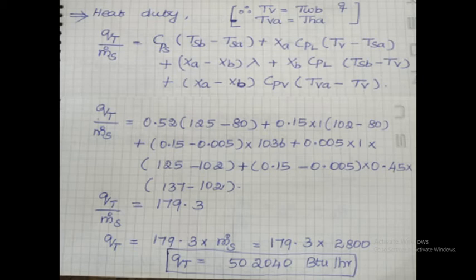TVA equals THA — that is the hot air outlet temperature, which is a calculated value of 137 degrees Fahrenheit. TV also equals TWB. Substituting all values, we find QT divided by M-dot-S equals 179.3. M-dot-S is the given mass flow rate of solids, so multiplying by M-dot-S, we finally get QT equal to 502,040 BTU per hour. This is the heat duty value.